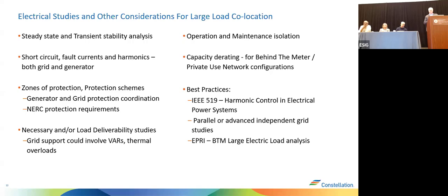otherwise achieving. So some of the best practices mentioned there, IEEE standard 519, highly important to be coordinated with the data center or other large load, because load fluctuations can flow backwards to both the generator and the grid. And in some cases, there are examples where those type of fluctuations have had grid impacts. And so making sure that the customer actually has all of the equipment within their facility to make sure that they stay within the bounds of the IEEE standards.